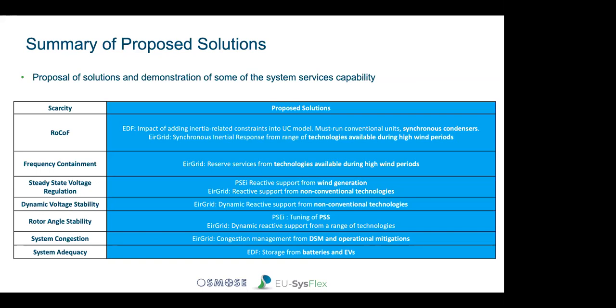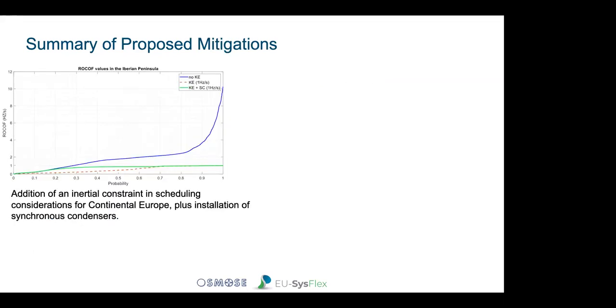On the next slide, without going into details, I've described some of the successes we've had in demonstrating different mitigations. The first is the simulation of the provision of synchronous inertial response, in this case by synchronous condensers, which we've shown can help significantly with frequency stability by increasing the level of inertia in the system and reducing the rate of change of frequency.